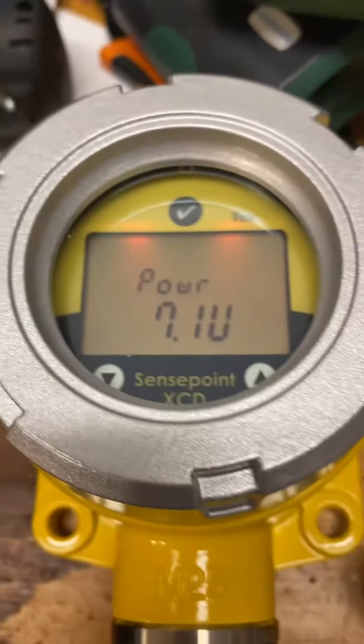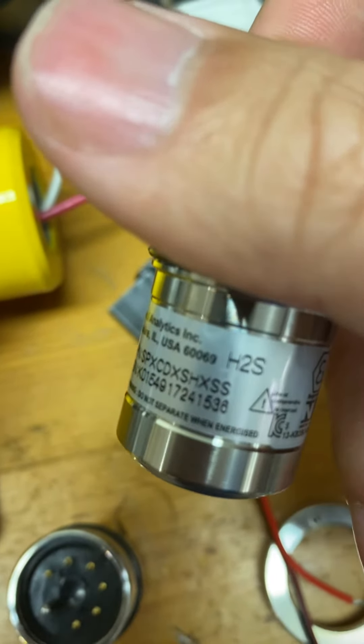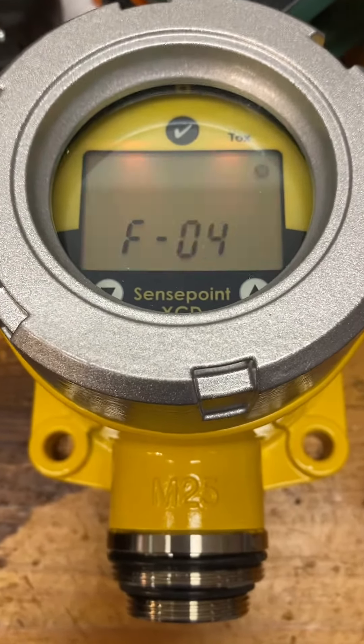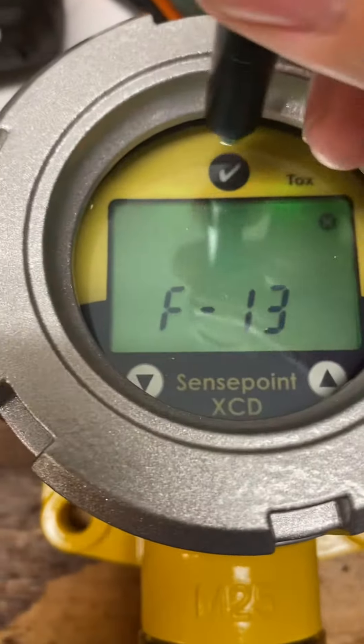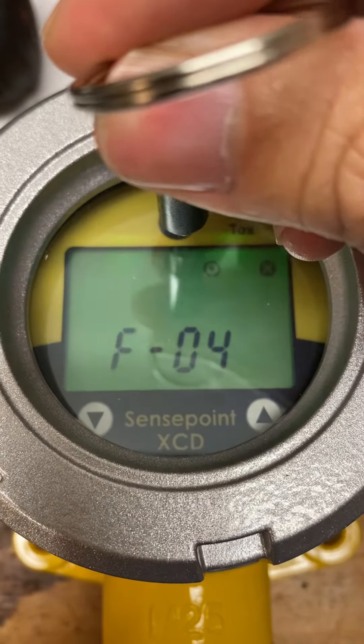Trying to program this XCD to actually read off of this O2 sensor. The unit was originally shipped with hydrogen sulfide, which we no longer use. Right now this is with no sensor inserted and it's displaying the failure code. But the issue is I cannot change the sensor type.